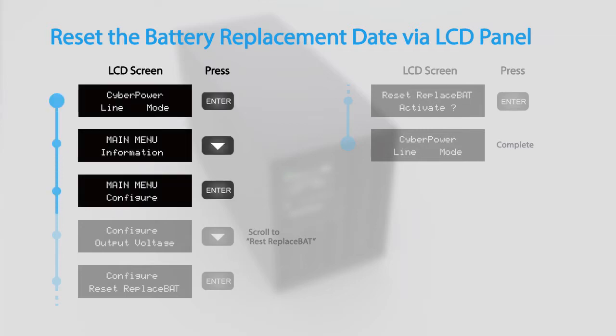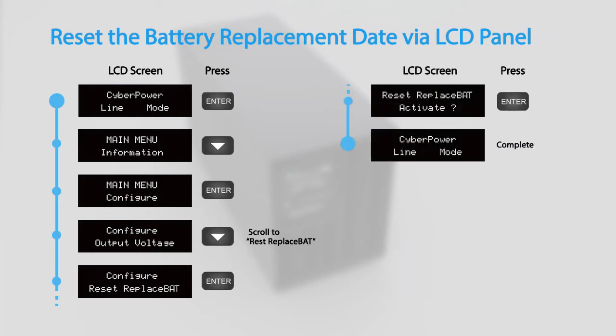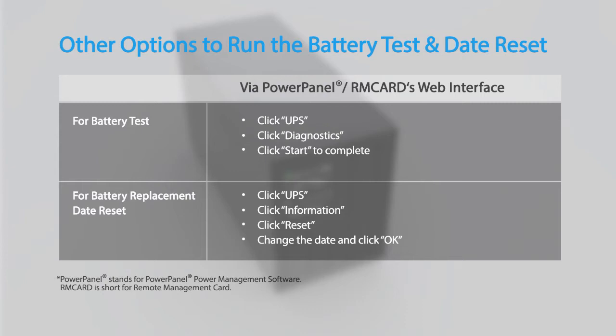Finally, to reset the battery replacement date, access the configuration menu and scroll to the Reset ReplaceBAT option. Press Enter to activate. You may also run the battery test and reset the battery replacement date by using the PowerPanel power management software or an installed remote management card.